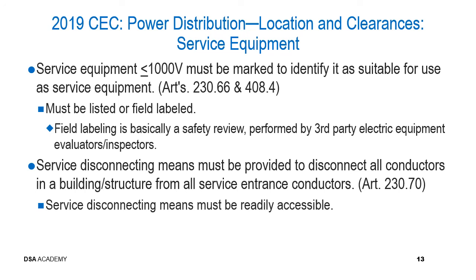Now we're going to talk a little bit about service equipment. Service equipment that is less than or equal to 1,000 volts must be marked to identify it as suitable for use as service equipment. This is identified in Articles 230.66 and 408.4. These must be listed or field labeled, and to clarify, field labeling is basically a safety review that is performed by a third-party electric equipment evaluator or inspector. This is a process that is acceptable in the California Electrical Code for the labeling of electrical equipment. So it basically carries the same weight as listing a piece of equipment from the manufacturer.